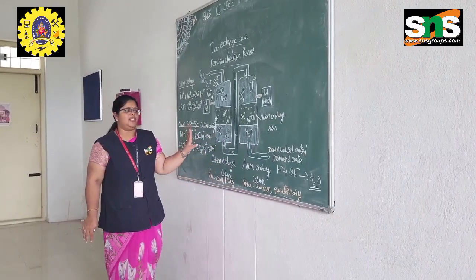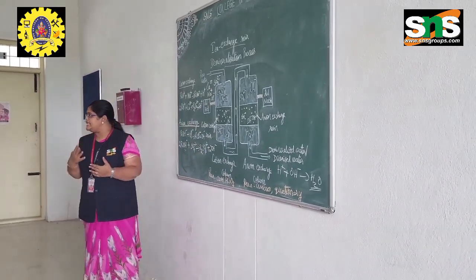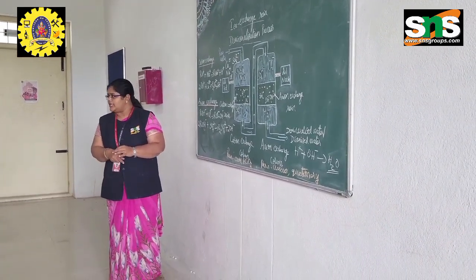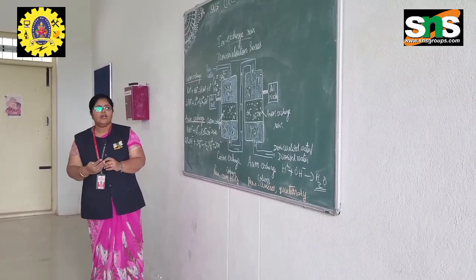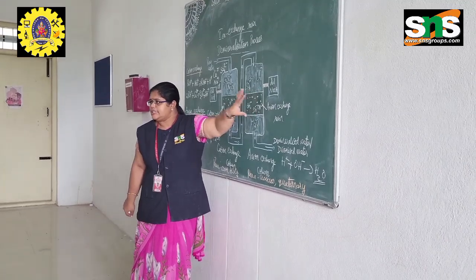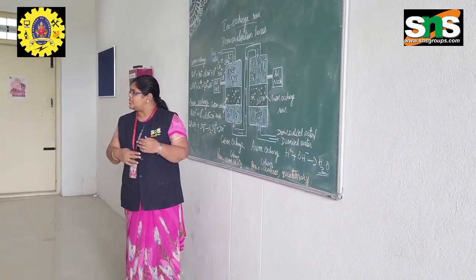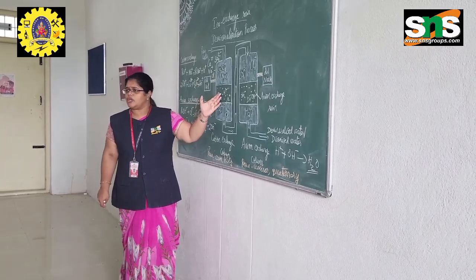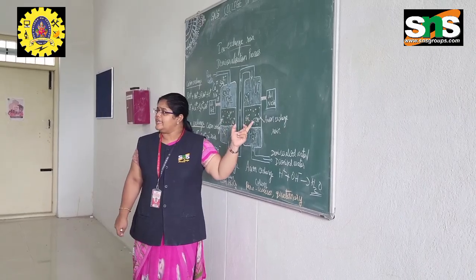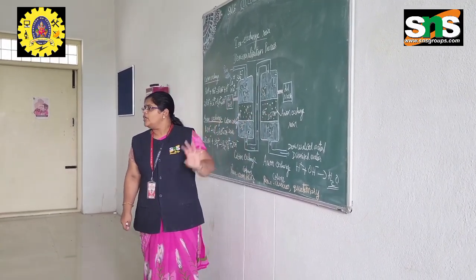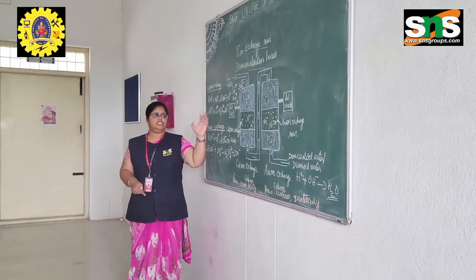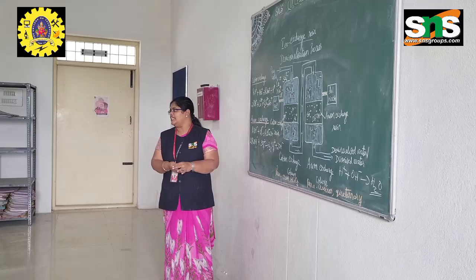Okay. So in this process, you are sending the raw water into the ion exchange first. Then after that you get the deionized or demineralized water. When this process is going on, after some time what will happen? These H plus ion and the OH minus ion in the resin will get exhausted. There will be an exchange process and you will have calcium or sodium salt or any other minerals over here. And here also sulfate, chloride or any other anions will be deposited. At that condition, it's called exhausted. Okay, can any one of you tell what is this exhausted and how you will regenerate in this process?